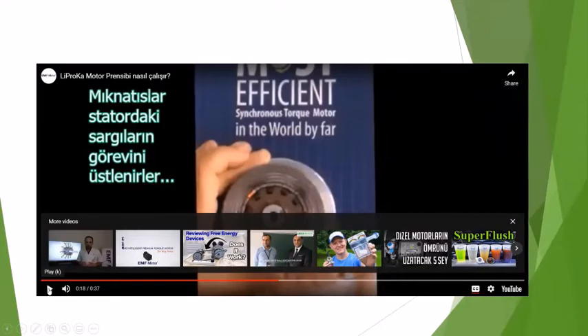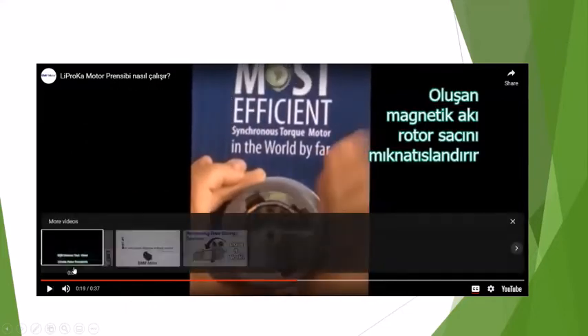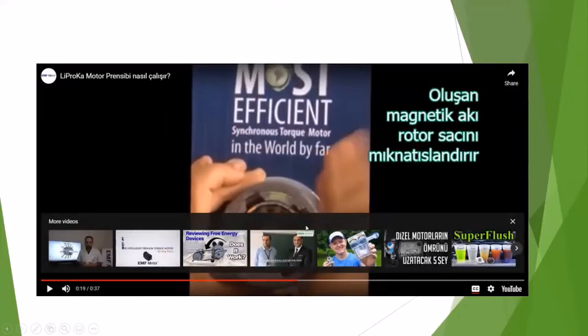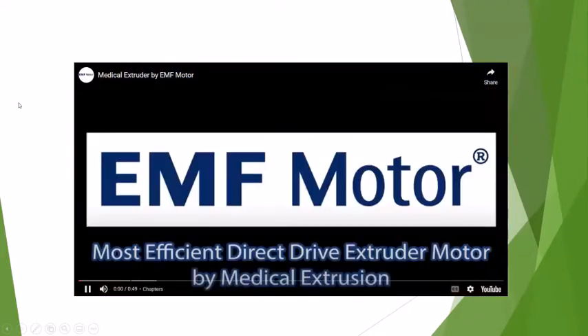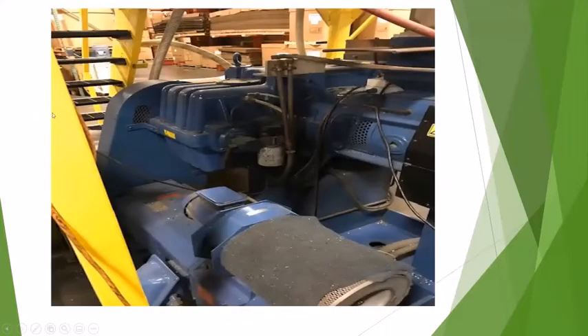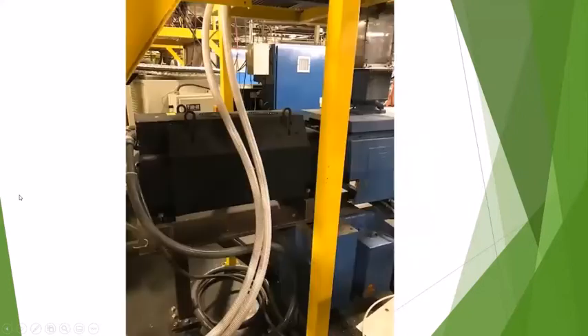So as you see here, as this turns, the actual rotor turns backwards, but they use a four-pole machine on the outside. They layer inner magnets in here, and then another set of magnets on the rotor. From that, the rotor turns backwards compared to the rotating field on the outside. And so what we had done is took this machine and tore all the gearboxes off and everything and directly connected it to the motor.